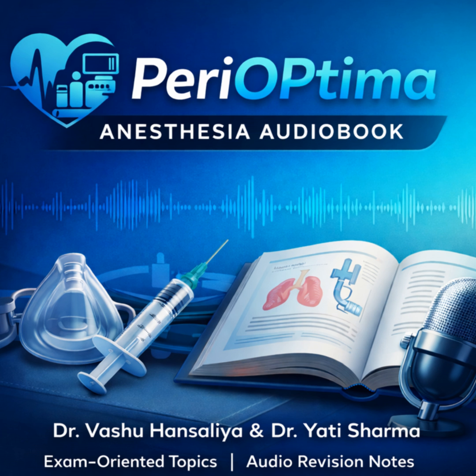A flow tube calibrated for helium, which has very low density, will be wildly inaccurate if you try to put nitrous, which is very dense, through it. What about the bobbin itself? I've noticed it spins. Why does it do that? Good observation. You'll notice small cuts or slots on the rim of the bobbin. The gas stream hits these and makes the bobbin rotate. This is a visual confirmation for you, the anesthetist. If it's spinning, it's floating freely in the gas stream. And if it's not spinning? It might be touching the glass wall, stuck by static electricity or a bit of dirt, and that could give you a false reading.